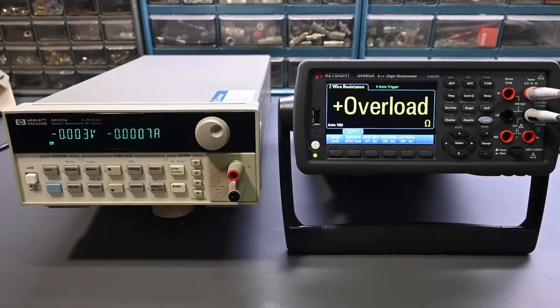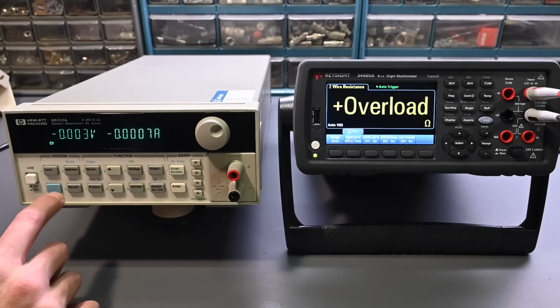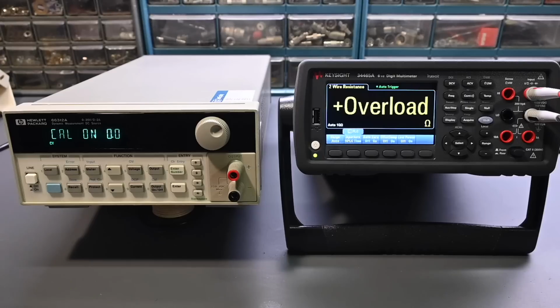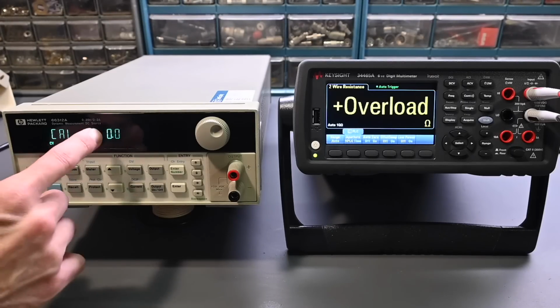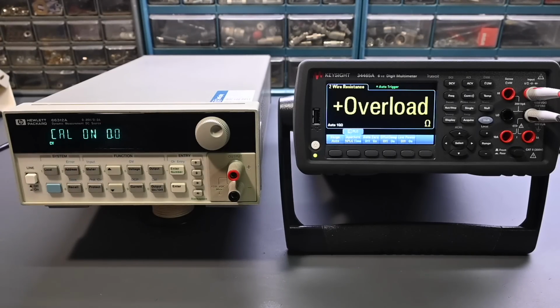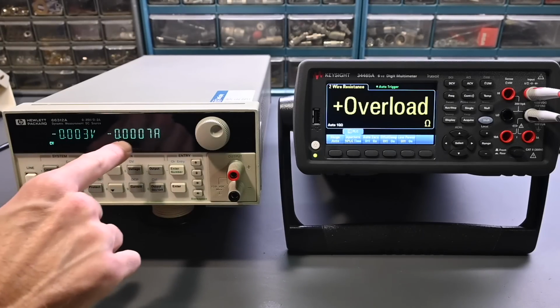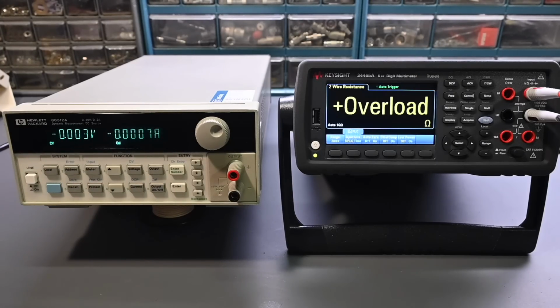It says to begin the calibration, press the shift cal, so shift and cal. Scroll to cal on, which we're at. And then it says to press enter, and assuming that the password is correct, and the password is set to 0, and that's the default, so let's find out if it has been changed or not. Enter, and yes, we're in. So it says cal. So if the password is incorrect, it'll say cal denied or out of range. And there's some internal switches that you can move to work around that kind of an issue and reset the password. Luckily, we don't have to deal with any of that.